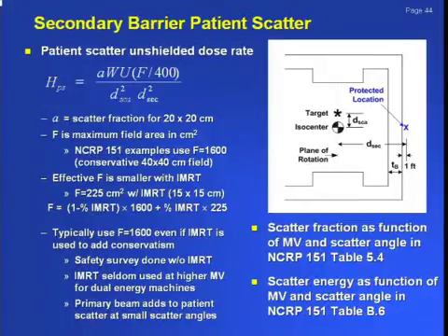But that becomes significant for IMRT factors, where we actually assume you're going to have no greater than an average of a 15 by 15 field for IMRT treatments. With that, you can reduce your patient scatter, because we know you're going to have a smaller field when you treat IMRT. If you did your IMRT calcs for patient scatter with a 40 by 40 field, you would overestimate the amount of patient scatter.